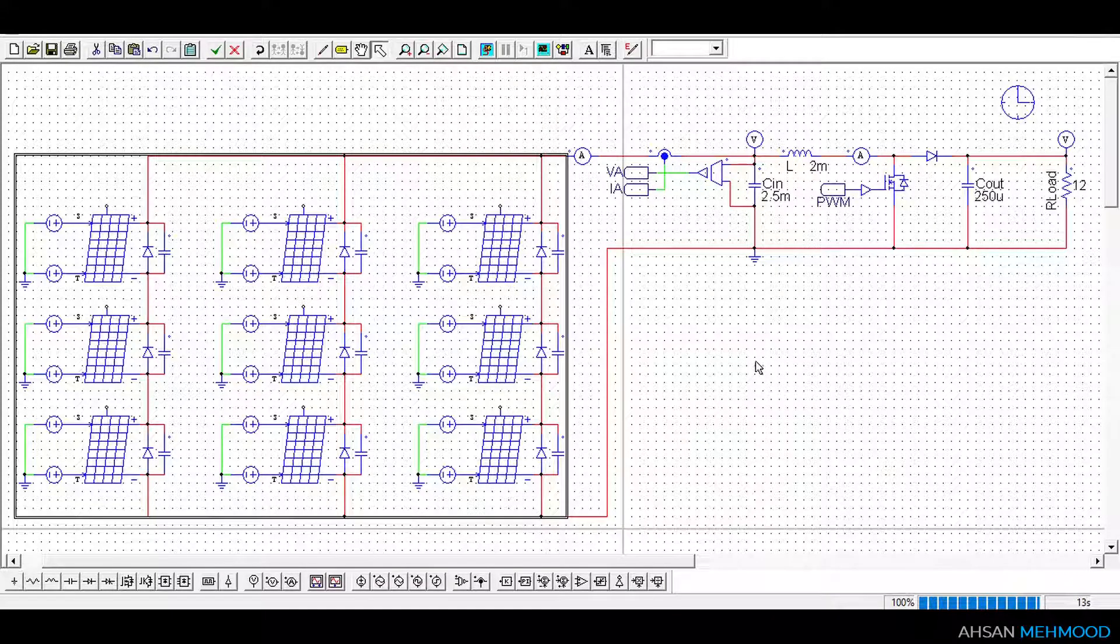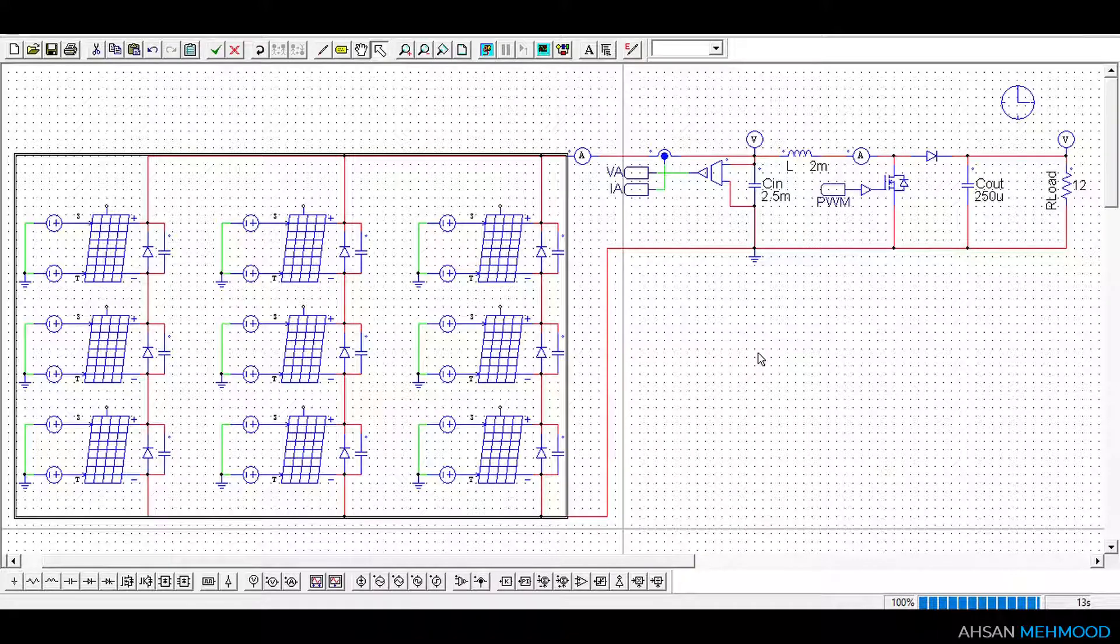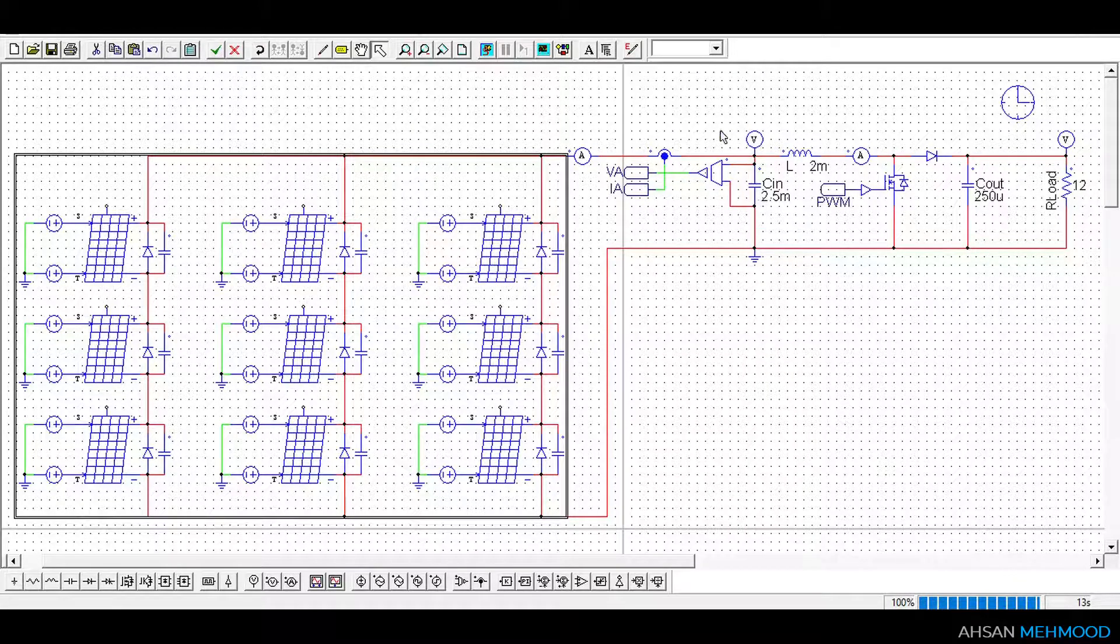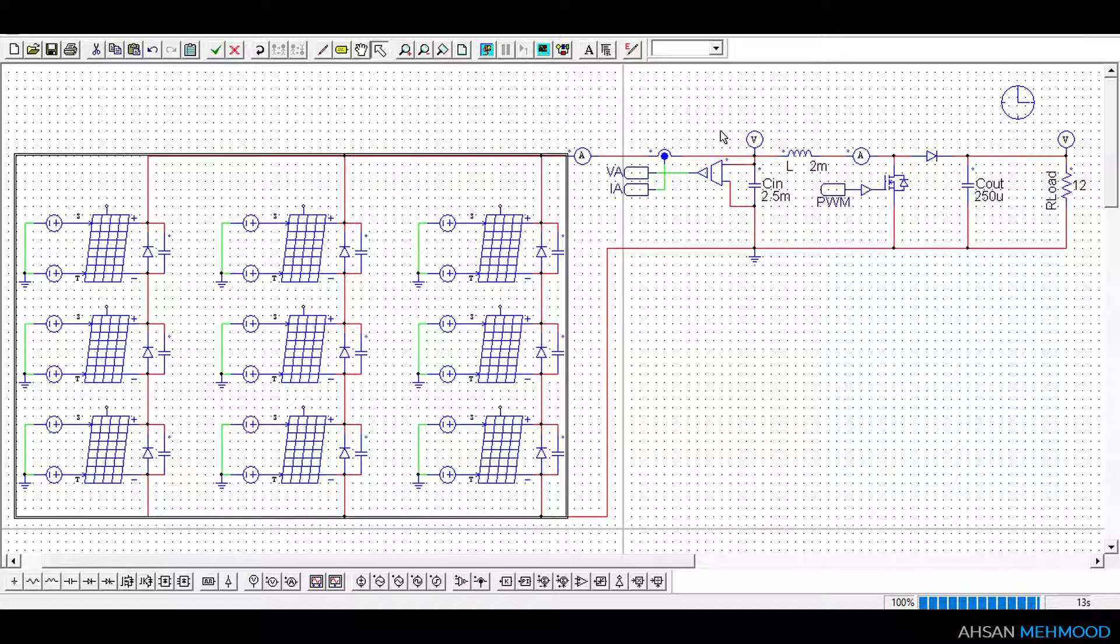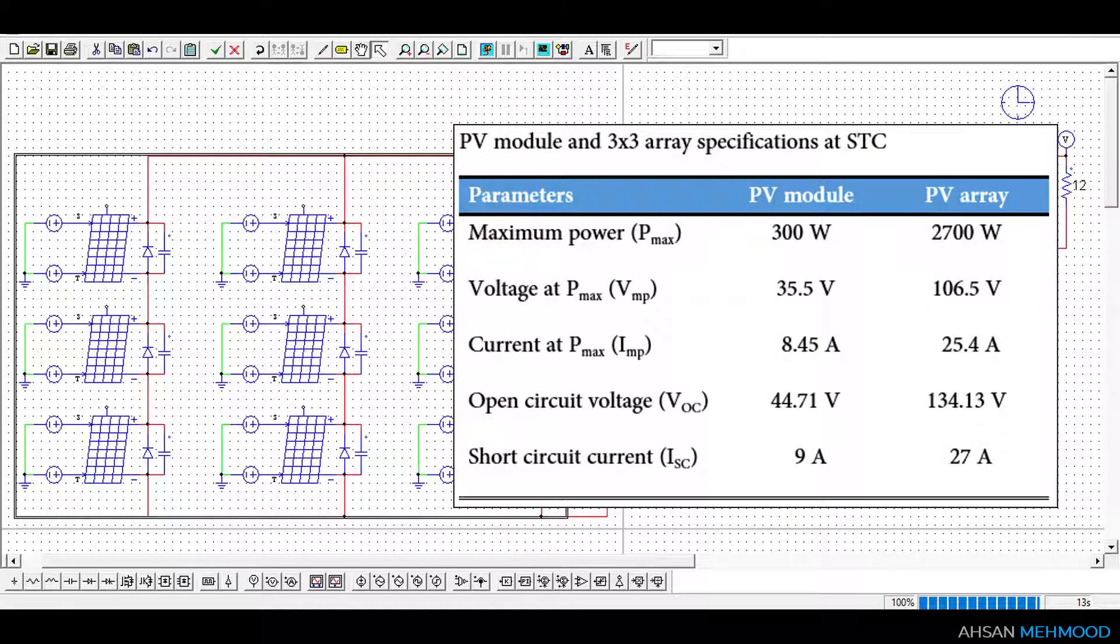The link to that video is provided in the description. This array delivers 2700W at MPP and standard testing conditions. Maximum power voltage and current of PV array are 106.5V and 25.4A respectively at standard testing conditions. The PV array's detailed specifications are shown on the screen.